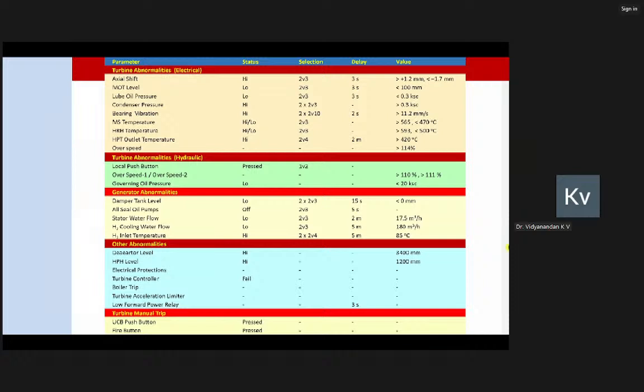This is the typical protection for 800 megawatt. More than 2 dozen signals are there. Not everything is shown in this slide because of the space crunch. But more than 2 dozen protections are there, and your Siemens 600 megawatt will have almost the same kind of machine. But to the best of my knowledge, the NTPC JIPT unit number 1, that is a Russian turbine, has the highest number of protections in NTPC, even a little more than the 800 megawatt.